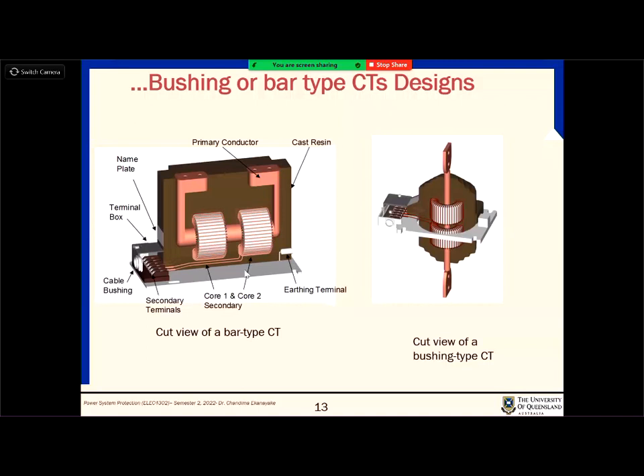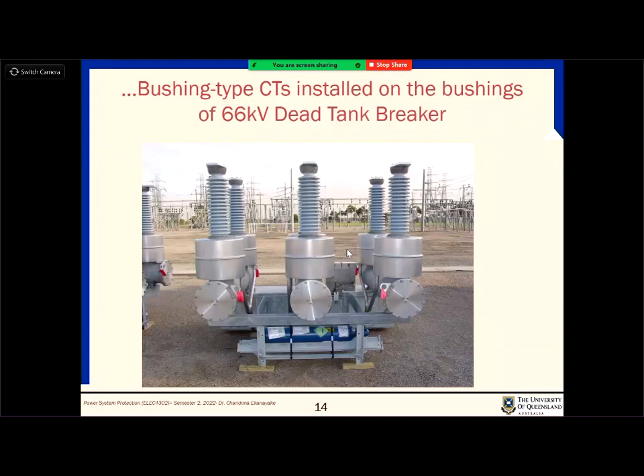Yeah, and then you can see another bushing type CT here. You can see that the current is going vertically through these two, and then you still have those two cores, right? But then there are these different designs in the real world. This is called a dead tank breaker, because the CTs on these breakers are the ones that measure the currents, right? And the breaker here is an old type of breaker.